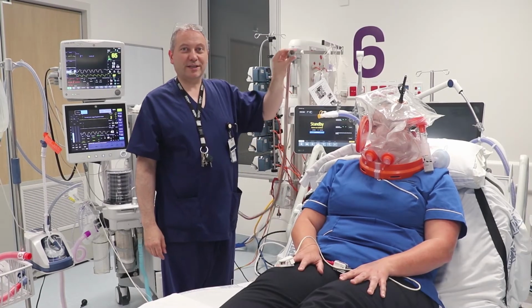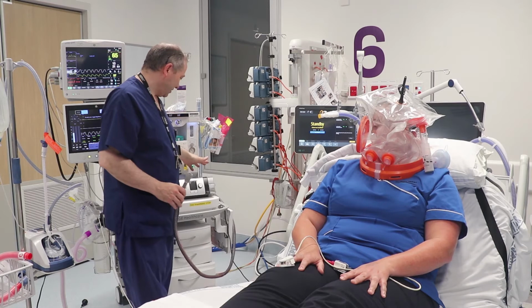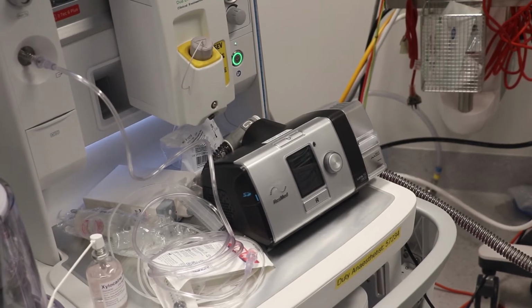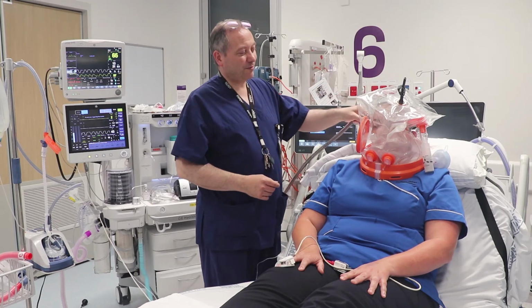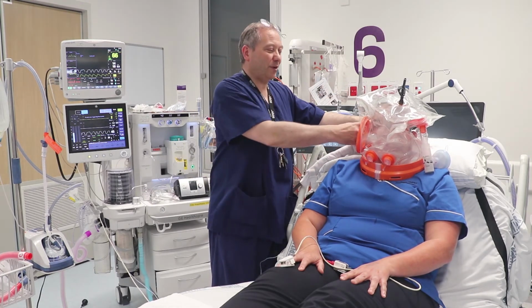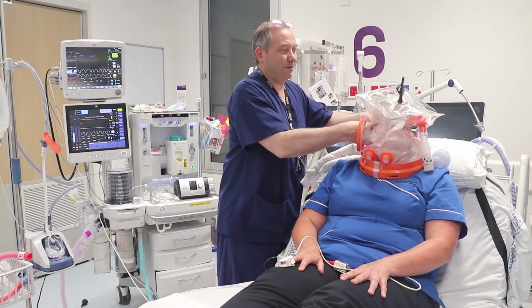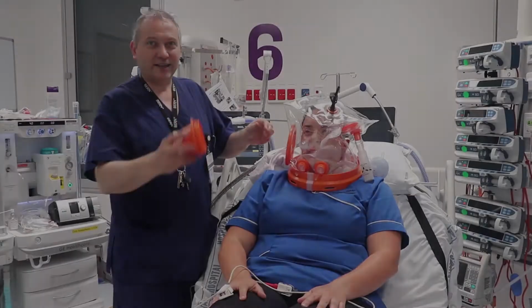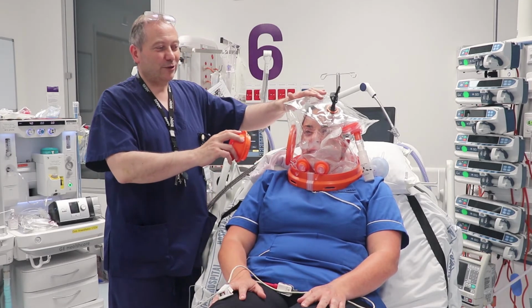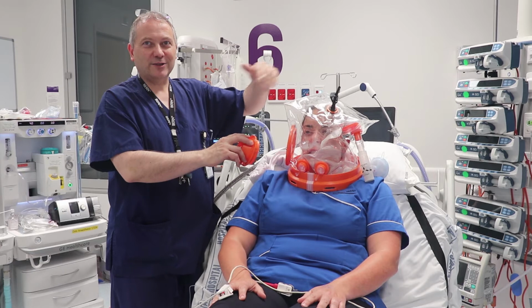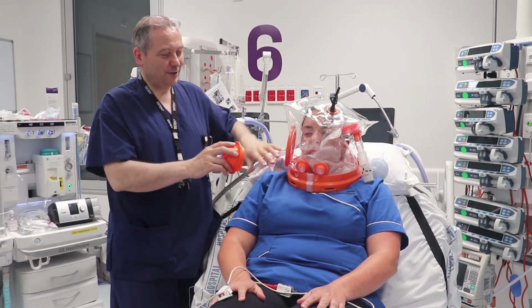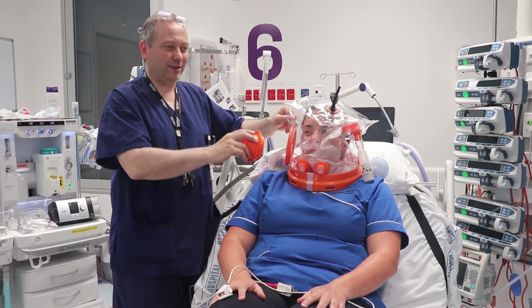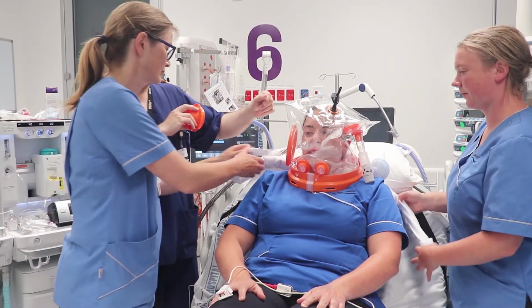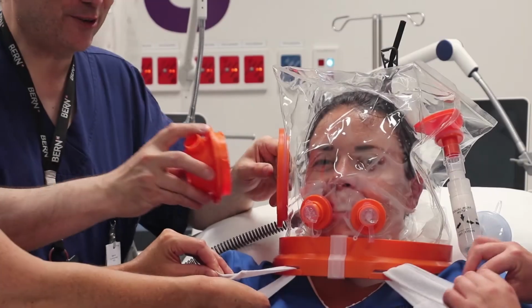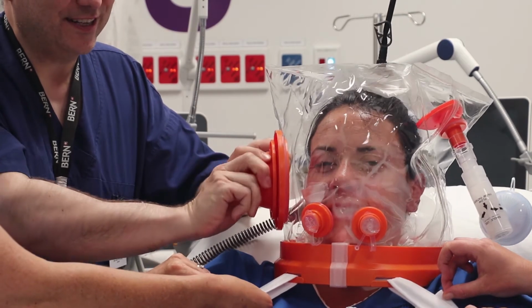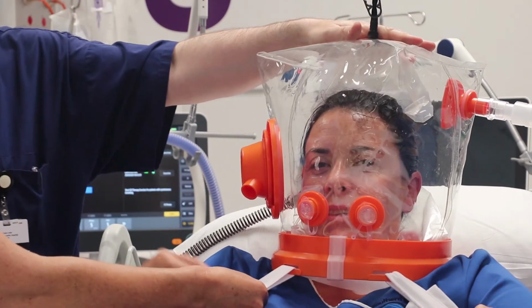Right, so the next thing we're going to do is connect our CPAP source, and in this instance we are using the ResMed Lumis machine, and we're going to attach the ResMed Lumis to the gas supply to Carla's right hand side. So next we apply the free breathe valve. When we do this, the helmet is going to fill with gas, and it's important that we have Louise and Sarah here to apply the straps, otherwise the helmet will rise up. So if you want to get the straps ready to apply, I'm just going to apply the free breathe valve and the helmet will inflate, and we may need to adjust the straps.